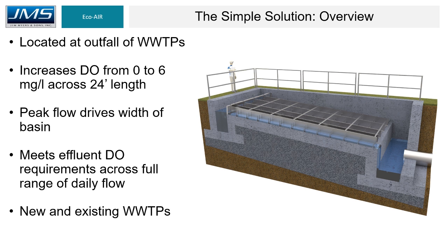The low profile cascade aerator is found at the outfall of wastewater treatment plants. We guarantee an increase in DO from zero to six milligrams per liter across 24 feet of length, with only two feet of fall from beginning to end. Peak flow determines the width of the LPCA, which in turn drives the width of the basin and concrete. The DO effluent requirement will be met across the full range of daily flow — if sized for 6 MGD, it will still achieve the effluent DO requirement at 2 MGD. The LPCA can be inserted into both new and existing wastewater treatment plants.